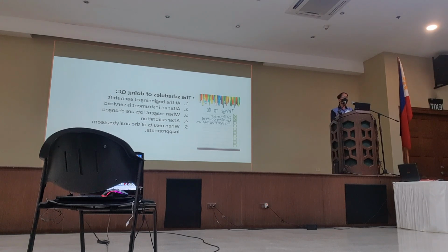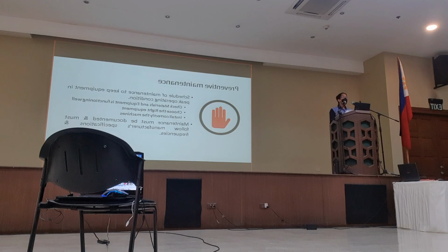So nakapag-calibrate na tayo, nakapag-control na tayo, now we go to preventive maintenance. Yung mga may motor dito, parang nagpe-preventive maintenance din sila. Wala pa yung problem, wala pa yung error, pero may ginagawa ka na to prevent the error from occurring. So meron kayong checklist sa laboratory. Tama? Itong equipment na to, na-check mo ba yung valve for this time? Na-check mo yung level ng mga reagent? Nilinis mo ba? That's an example of preventive maintenance. And the rationale for this is to preserve or prolong the longevity of your instrument.